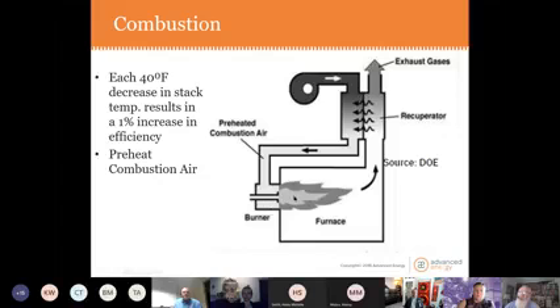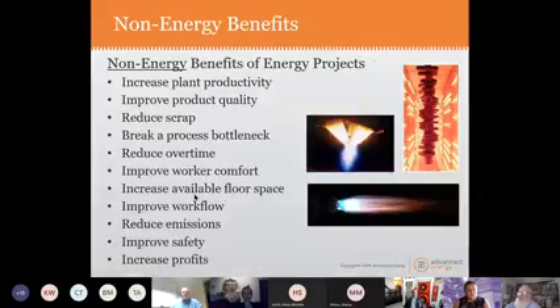Here's just an example. You got a combustion here, some type of furnace or boiler. This heat goes right up the stack. Well, if you bring your air, you have to blow air in here to make this combustion happen. So if you have a recuperator where the stack heats this incoming air, about every 40 degrees you can pull out of this exhaust gas, you can increase the efficiency by 1% of the combustion. So that's a very easy, again, retrofitting this might be expensive. If you had a new project, you would definitely want to buy something with preheated combustion air, just something to think about. All this waste heat, though, can you preheat water? Do you need lots of hot water? Maybe you put a water to flue gas heat exchanger here or something like that.